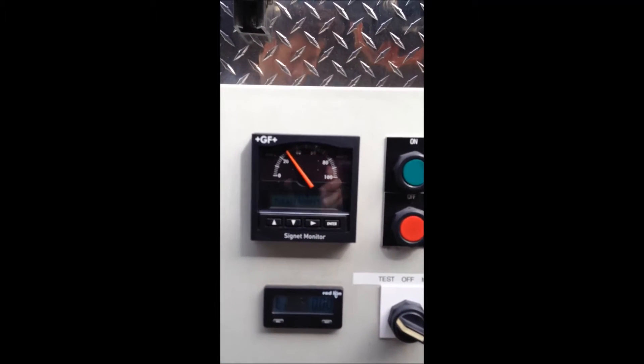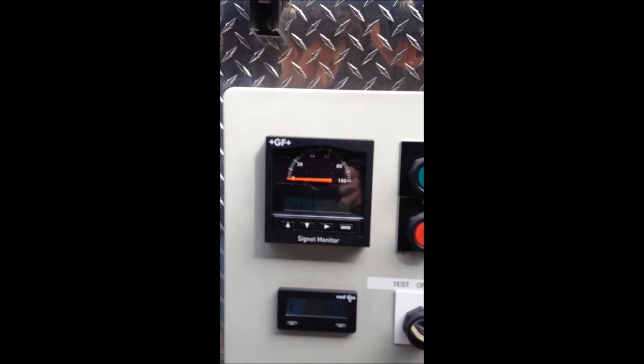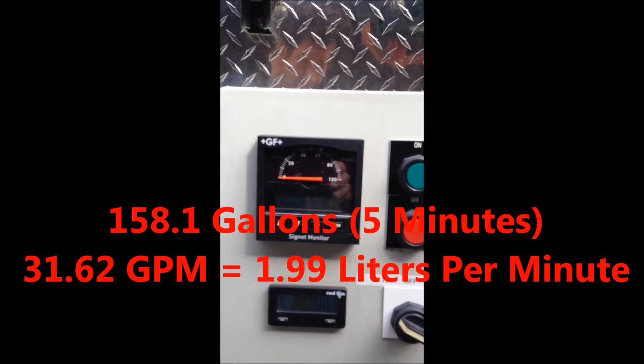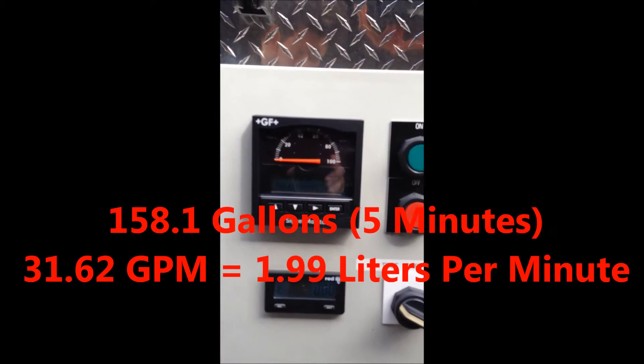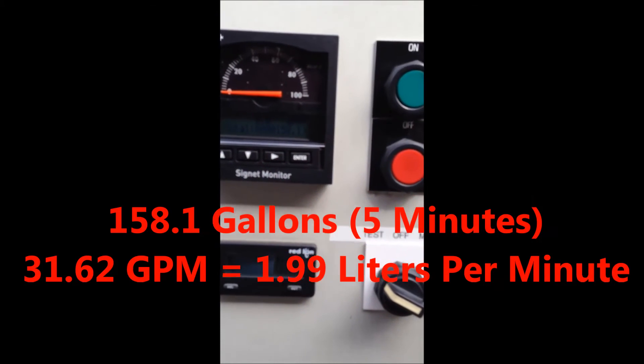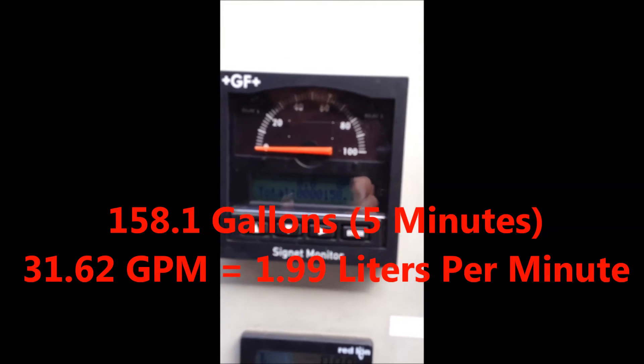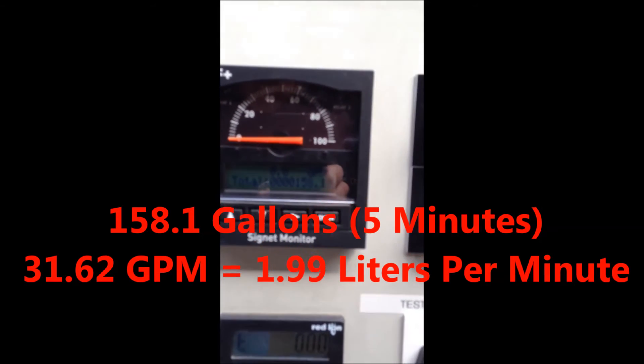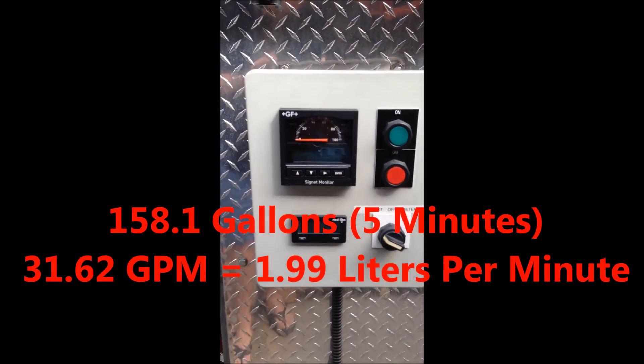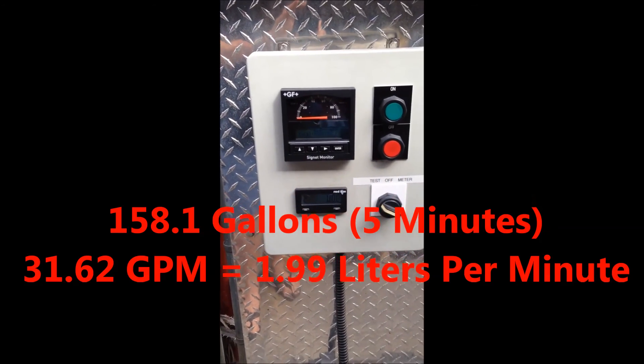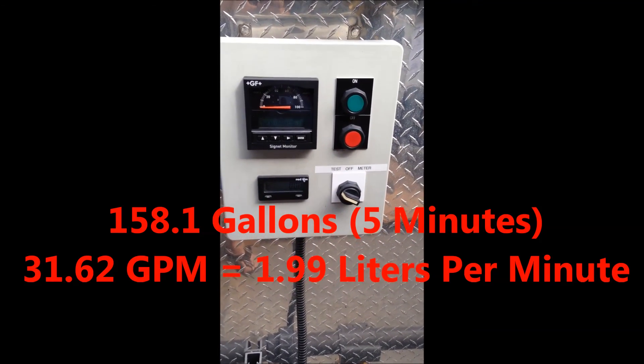Our test is now complete. Our test concluded that we did 158.1 gallons in a five-minute interval. You can hear the pump still running right now. I'll do the math in just a minute.